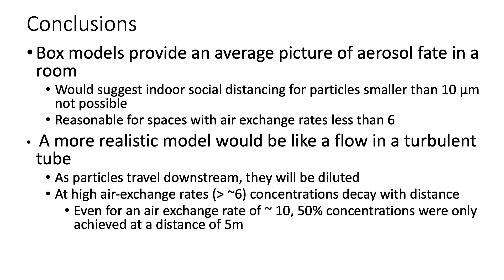The box models, however, would suggest that social distancing of particles, small particles less than 10 micron, is not possible. But what we are finding from experiments is that the box models are actually reasonable when the air exchange rates are low, less than about 6. A more realistic model would be one where we consider the flow in the room to be similar to flow through a turbulent tube. In a turbulent tube, as particles are traveling through the tube, they're getting lost and the concentration is going down. In a room, these particles are continuously getting diluted by fresh air that's being injected by all these vents throughout the room. When the air exchange rates are about 9 or so, greater than about 6, we believe that the box models start failing.